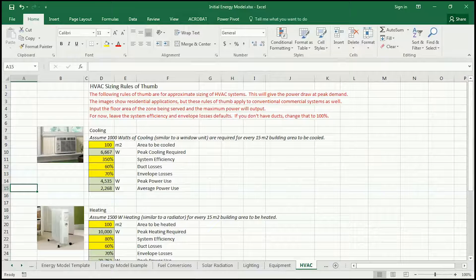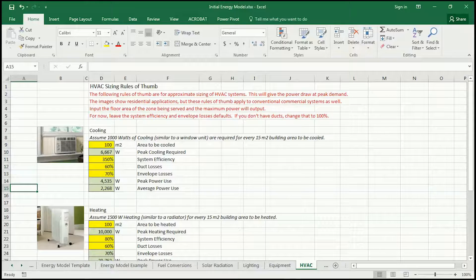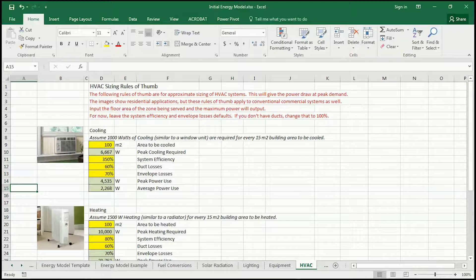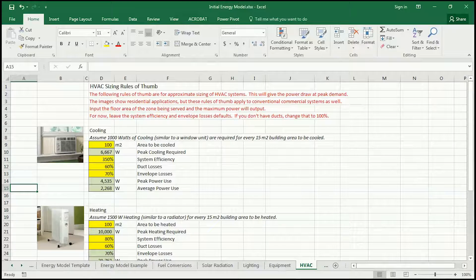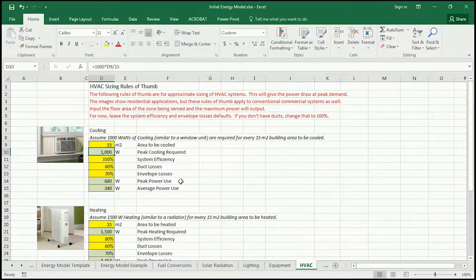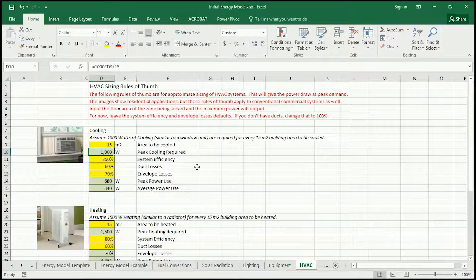This logic can be applied to much larger buildings and systems. For instance, this is a standard residential window unit air conditioner, and that would be sufficient to cool about a 15 square meter room. That supplies about 1,000 watts of cooling. So if I input 15 square meters, that's going to show that 1,000 watts of cooling is required.